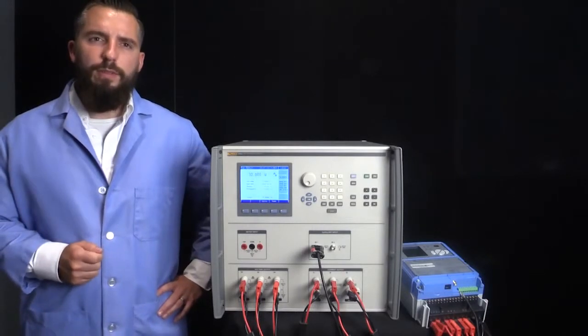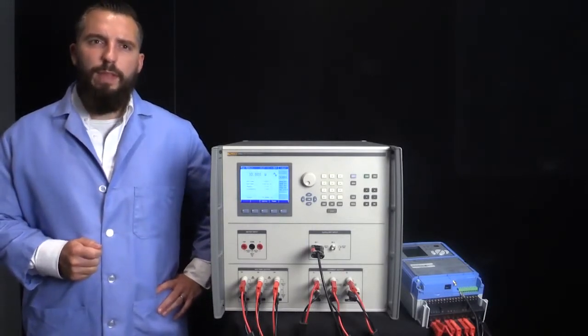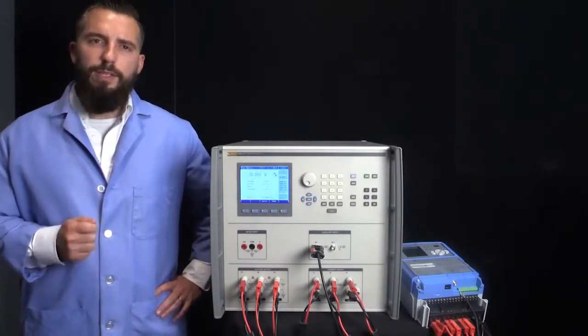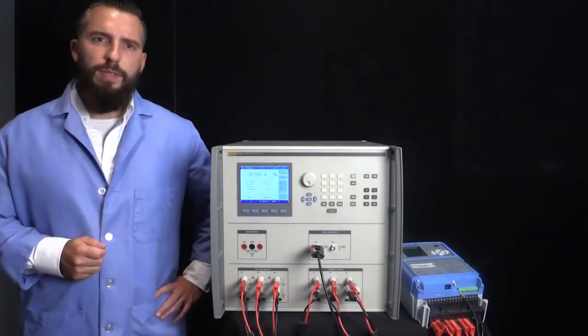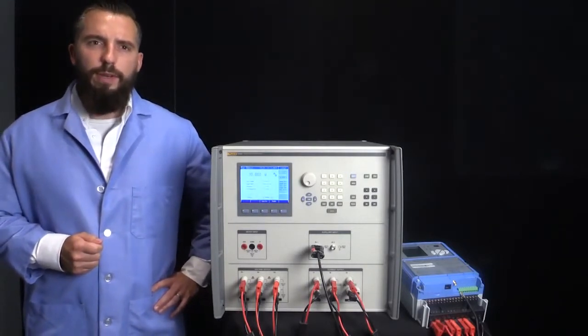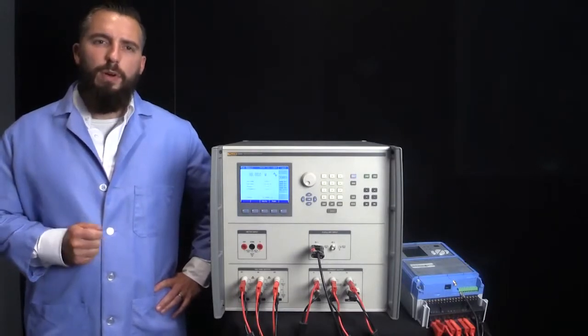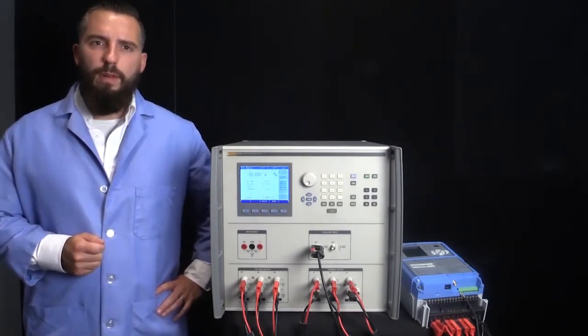This is mainly due to the process required to fully test and verify the output of the meter. Energy meters, almost without exception, use a technique of generating pulses to indicate the amount of energy they have measured. Each pulse represents a specific number of watt hours.